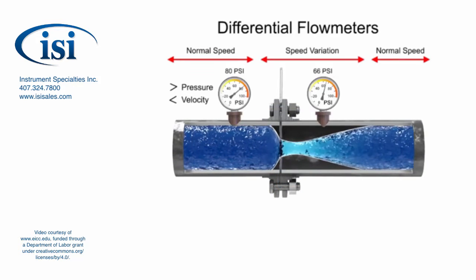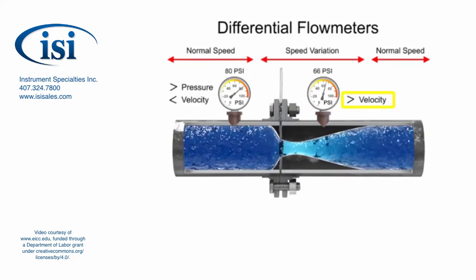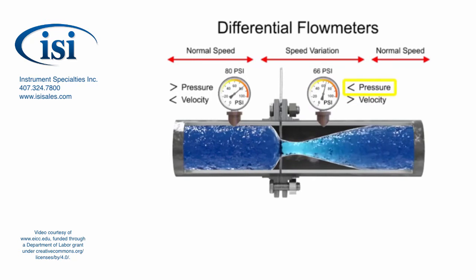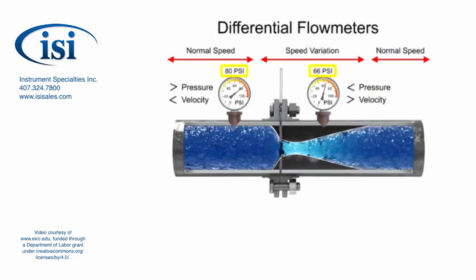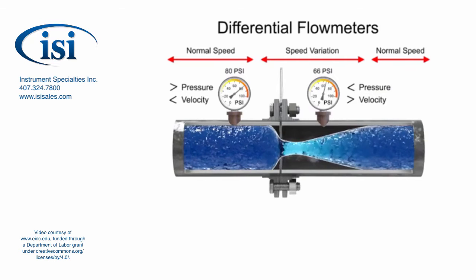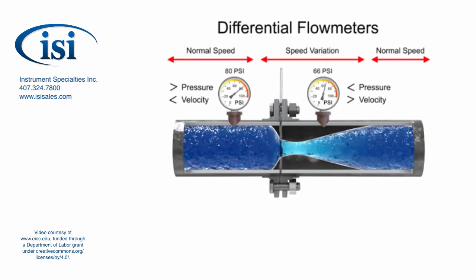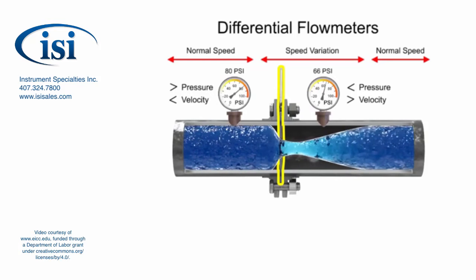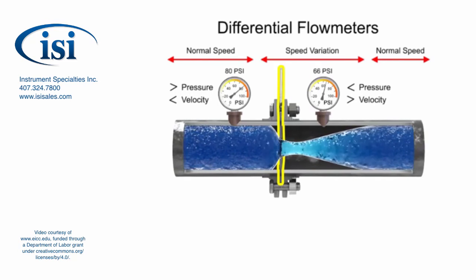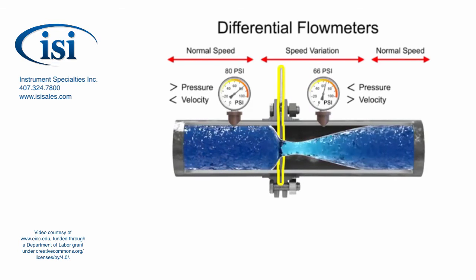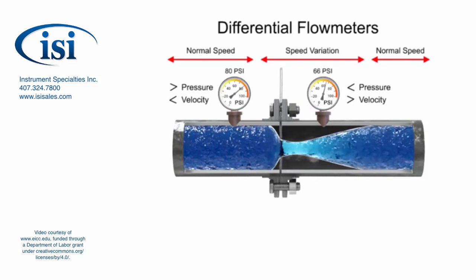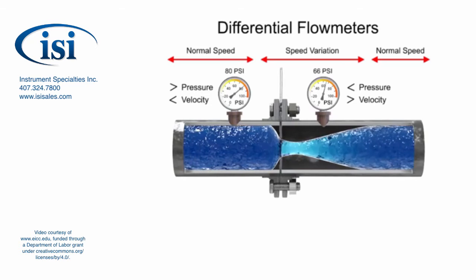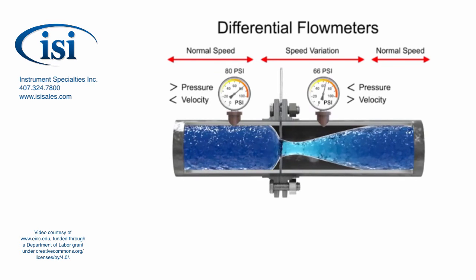Applying Bernoulli's principle, the increased fluid velocity results in a decrease in pressure. As the fluid flow rate increases through the pipe, back pressure on the incoming side increases due to the restriction of flow created by the orifice plate. The pressure of the fluid at the downstream side of the orifice plate is less than the incoming side due to the accelerated flow.